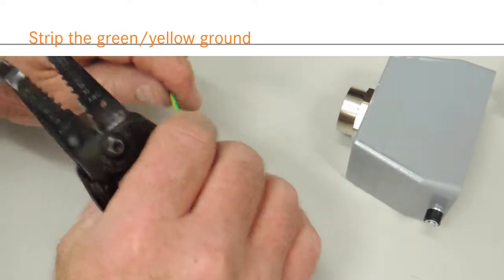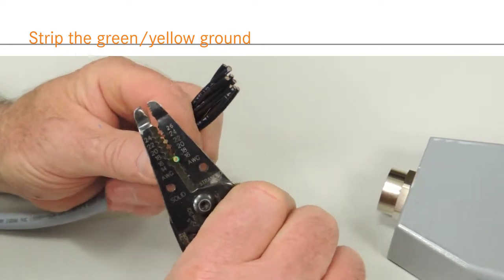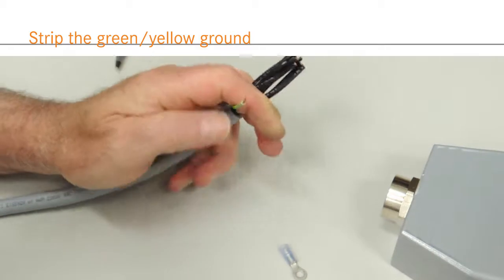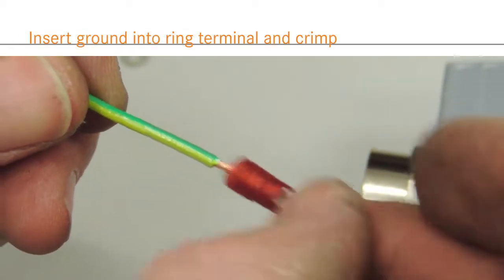To terminate the green-yellow cable ground, measure against the ring terminal and strip the wire 3 eighths of an inch. Insert the wire into the terminal. You should be able to see the stripped wire through the end of the ring terminal.